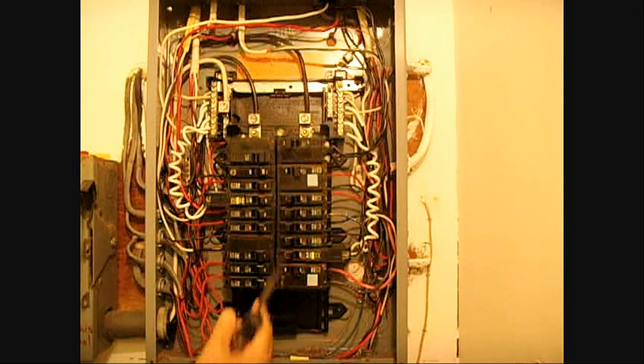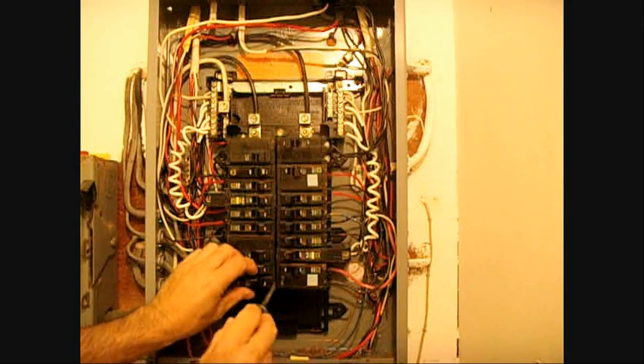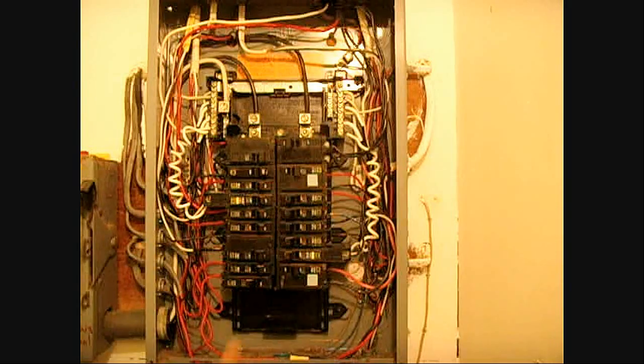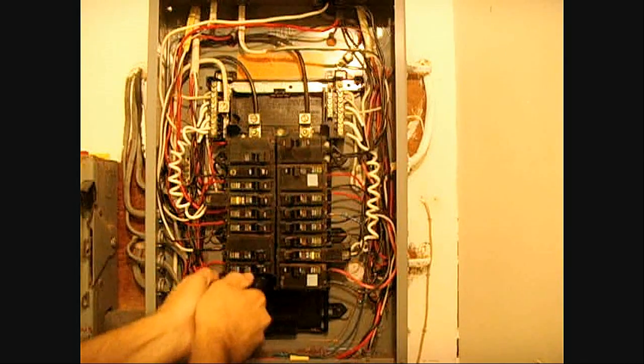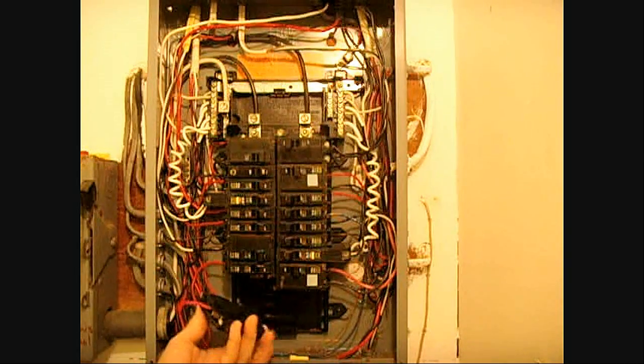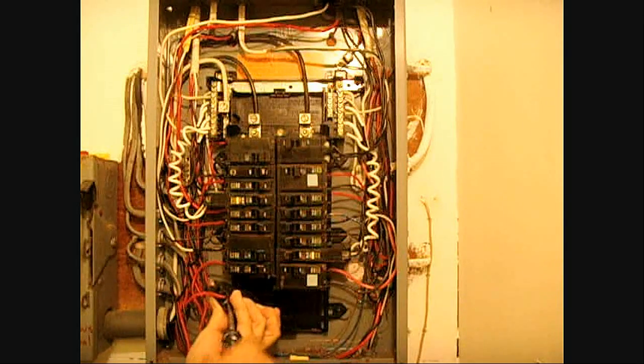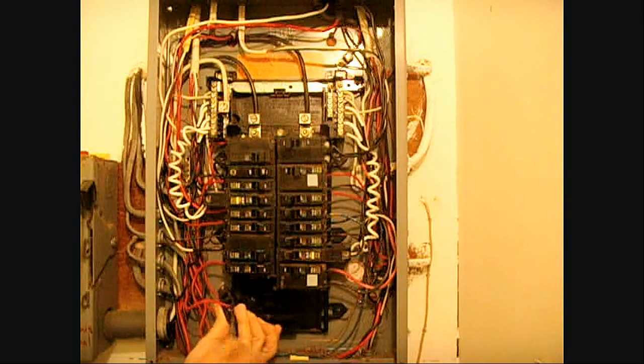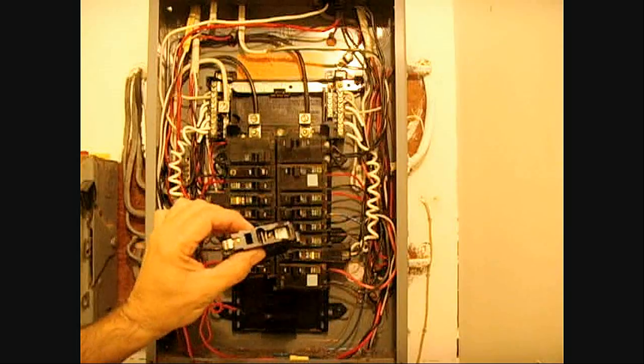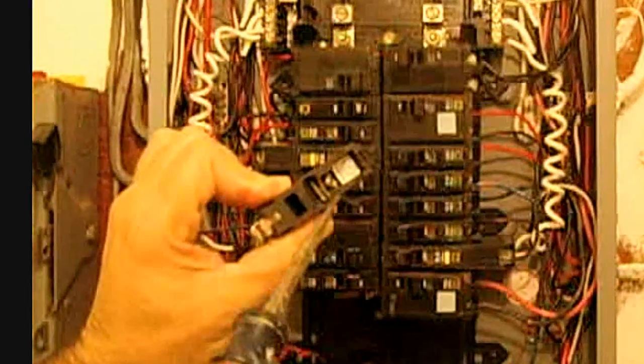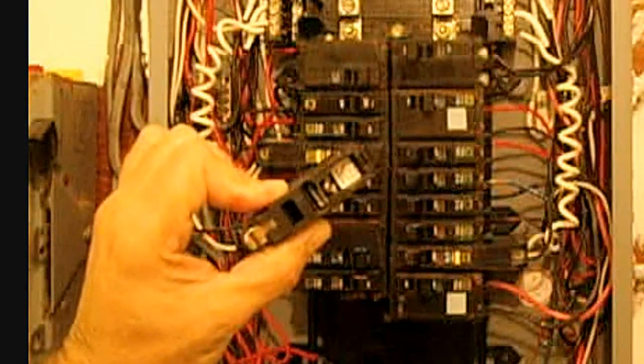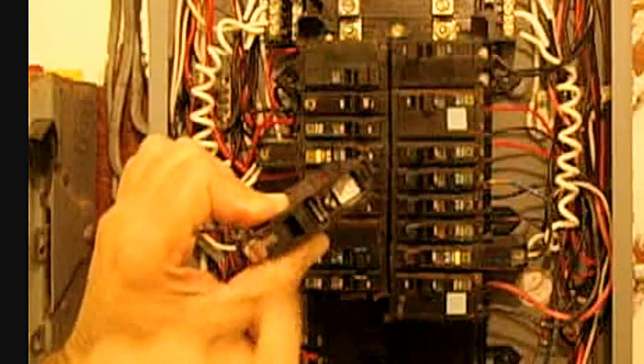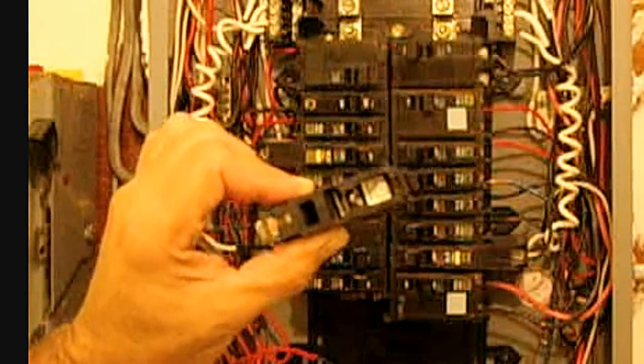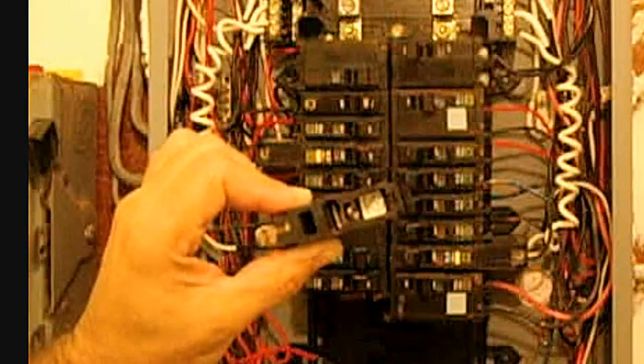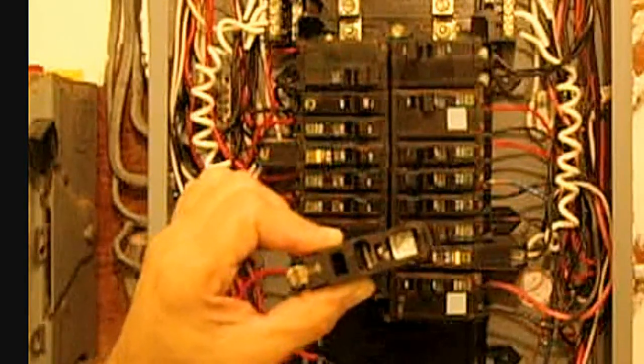Now a lot of breakers, I'll take this one out and show you. Just pop it out gently. Alright. Pull it hard like that. Let me take this one off altogether. Show you closer. Alright. If you look inside the breaker, you're going to see there's actually two places to put a wire. You can put one on that side or on that side. So even though it's designed to hold two wires, they only want you to have one wire in that connection.